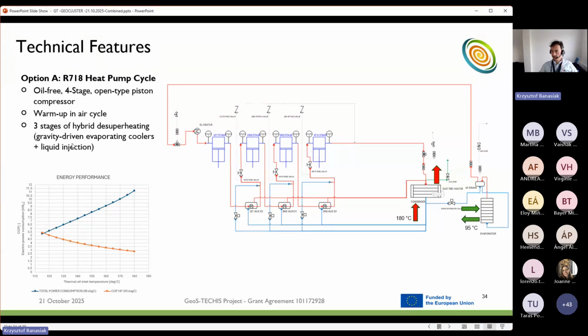Last but not least, there's the necessity of desuperheating after each compression stage, which we resolve with a nice solution using gravity-driven auxiliary evaporators that handle the desuperheating for us. In principle, they require no control. Another advantage is that by desuperheating to the condenser, we increase the COP of the cycle.